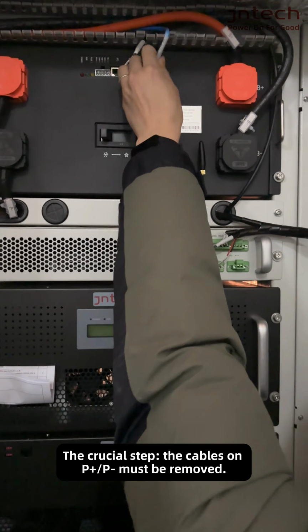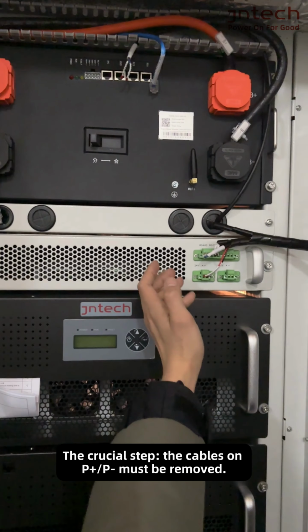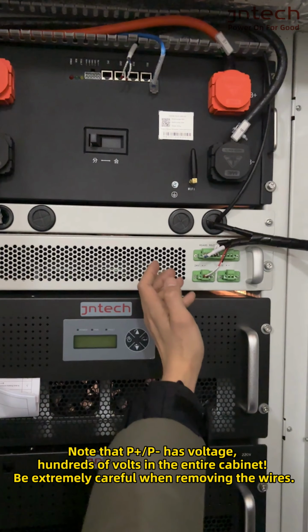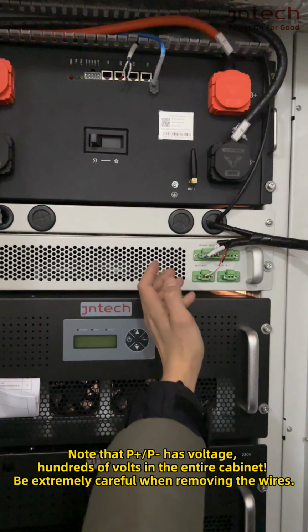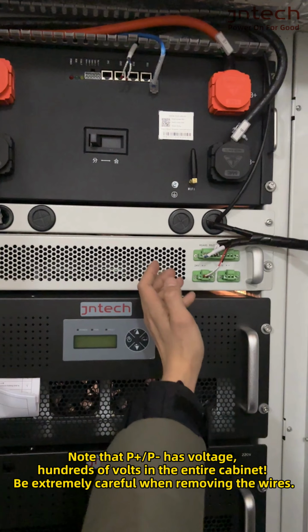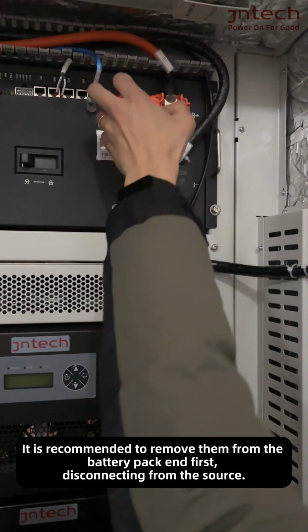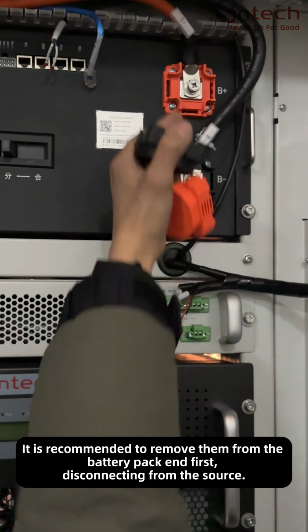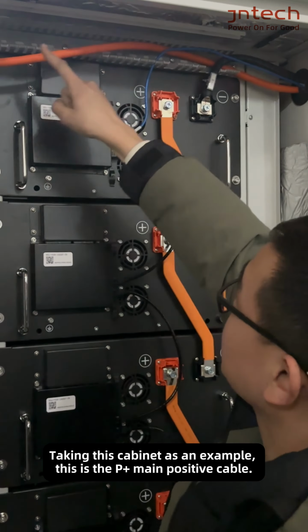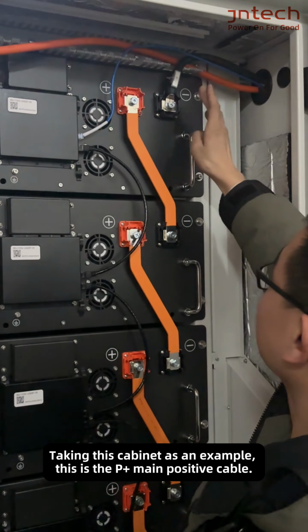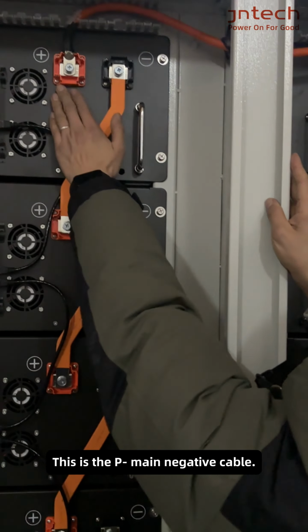The crucial step, the cables on P+/P- must be removed. Note that P+/P- has voltage, hundreds of volts in the entire cabinet. Be extremely careful when removing the wires. It is recommended to remove them from the battery pack end first, disconnecting from the source. Taking this cabinet as an example, this is the P+ main positive cable. This is the P- main negative cable.